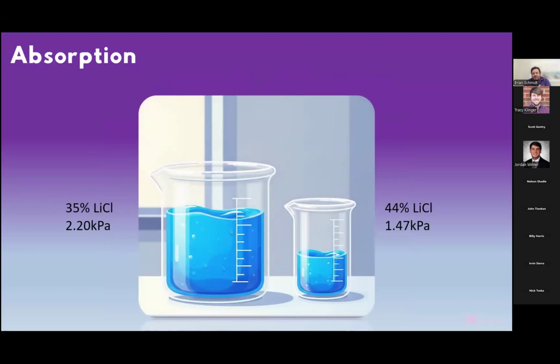And this is just showing the vapor pressure at different concentrations. The more concentrated we get, the lower the vapor pressure. The lower the vapor pressure, the more affinity we have for absorbing moisture. So at 44% in solution, we're at about 1.47 kilopascals. And at 35% solution, we're about 2.2. Again, atmospheric conditions are much higher than this. So the more concentrated we get through adding heat on the regeneration side, the more moisture we can absorb.